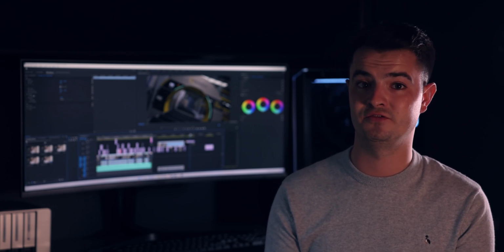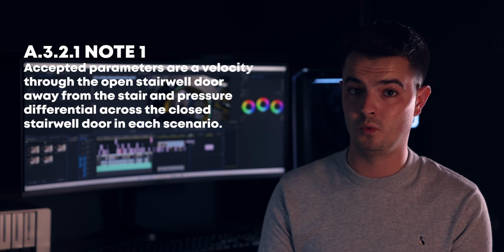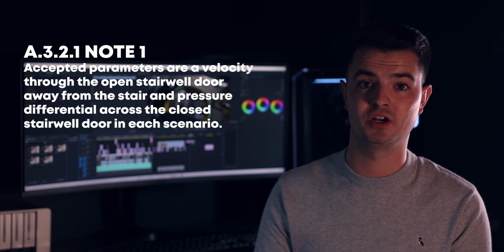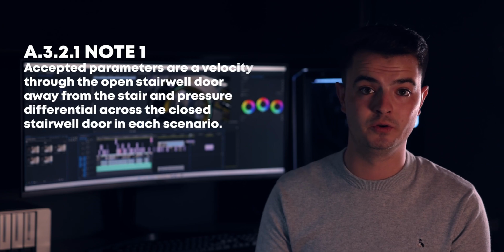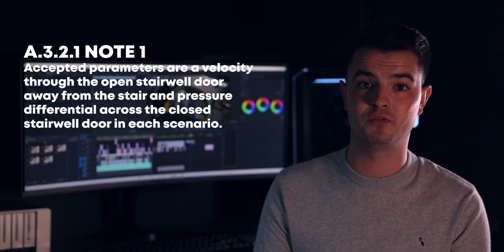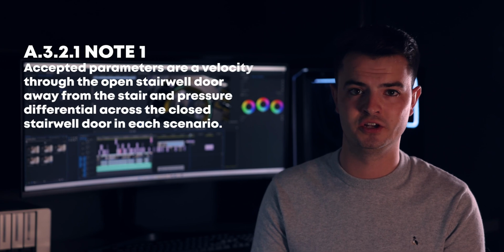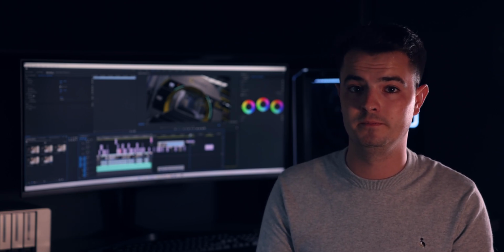Third, we have a reference to MSVS systems acceptability parameters as follows. A.3.2.1 note 1, accepted parameters are a velocity through the open stairwell door away from the stair and pressure differential across the closed stairwell door in each scenario. This strikes me as slightly unusual, as typically these parameters would form part of the test criteria for pressure differential systems rather than MSVS systems. Whilst we would still measure these criteria when we're carrying out tests on an MSVS system, they aren't usually our design criteria, so I'd like more clarity around this point.